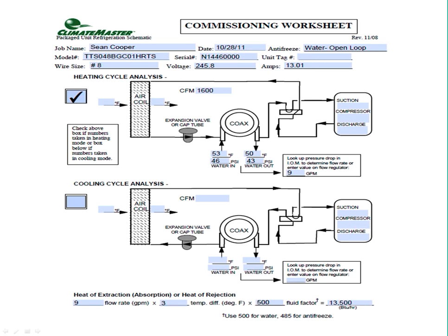Next, you want to put in your entering and exiting fluid temperatures. So probe your digital thermometer into the PT ports and record those temperatures. Again, after that minimum 15-minute runtime, full tilt, Y2, high speed if it's a 2-speed, and the hot water generator has been disabled. So in this case, we have an entering fluid temperature of 53. It is exiting at 50.